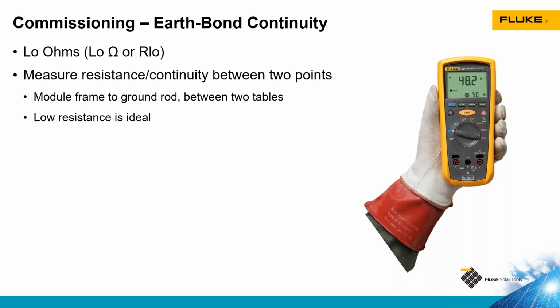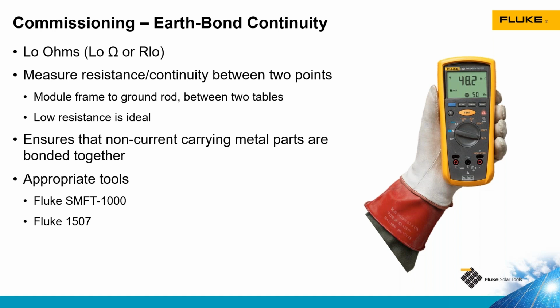And in this test, I'm using ohms as my unit of measurement, and I'm looking for low ohms, which is low resistance. And these metal parts need to be bonded together because if they're not, and if there's a ground fault, it doesn't have an easy path to ground. And if someone were to touch that piece of metal part, they're going to become that easy path to ground, which is a safety hazard for the technician, and that's what causes electrical shocks and electrocution. Also, some overcurrent protection devices like circuit breakers need that return path to ground in order to operate properly.